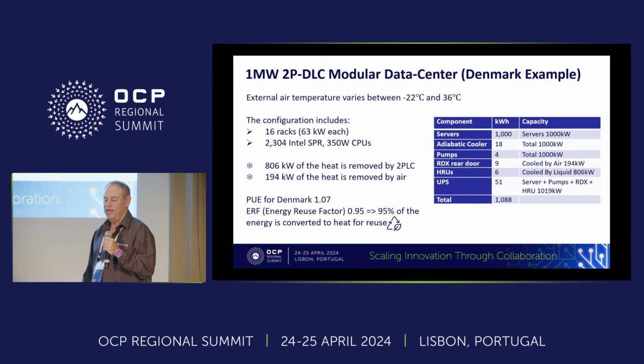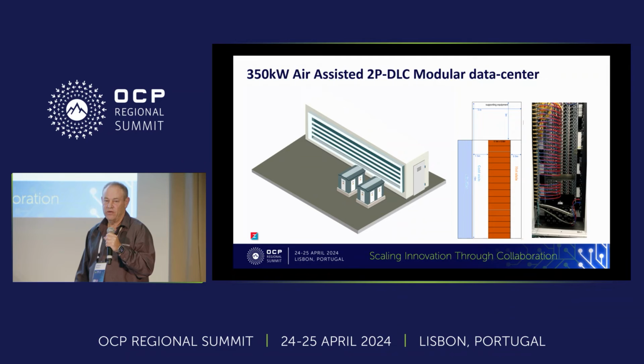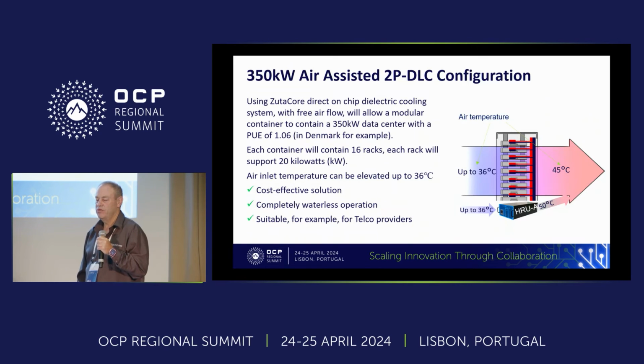So in this example, we see that a 1 megawatt data center is cooled by water. So you're cooling water outside, streaming the water in. And we show another example of a data center that is actually air-assisted cooling, meaning there is no water in this facility at all. This is air coming into the data center, cooling the servers, cooling by direct-on-chip liquid cooling, air-assisted, and moving out from the data center, as you can see here. So air can come in at up to 36 degrees in this case, and move out of the modular data center at 45 degrees. And the reason it's only 350 kilowatt is because that's the ability of air to cool it, because we couldn't get air lower than 36, it wouldn't make sense.